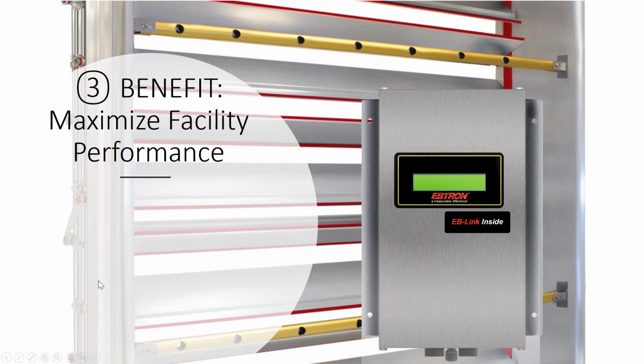One thing that I think is really important, and we're seeing a lot more nowadays, especially with big facilities, be it campus universities, is how to improve the facility performance and the facility efficiency. And again, I said you can't manage what you don't measure. I talked about the issues with dampers, right? You have hysteresis, but you also have dampers that bind over time. You have economizers that don't always work. You have fans, you might have a fan array, and you have fans that might fail within that array, right?